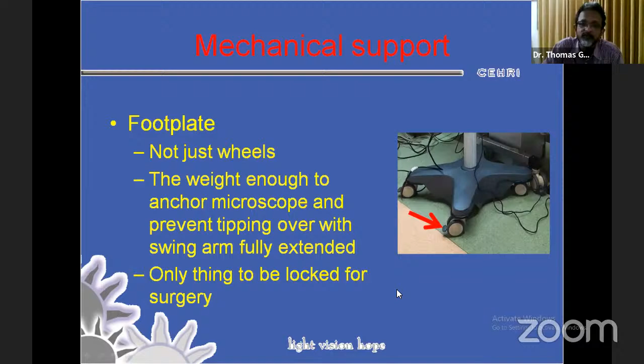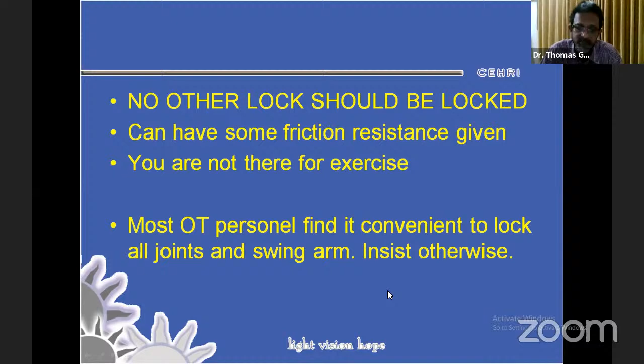No other parts of the microscope should be locked, and one can have some friction resistance given by those turning knobs, essentially screws that add friction to the movement, so that you have a certain amount of non-jerky movement, but it should never be locked. You're not there for exercise, you go to the gym for that. Most OT personnel would find it convenient to lock all joints and the swing arm for their convenience. Please insist otherwise, because you need the movement while you're doing the surgery.